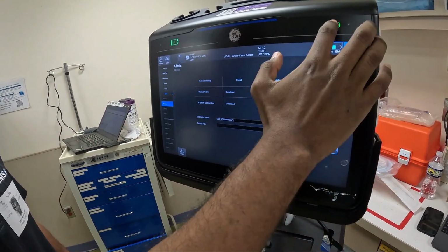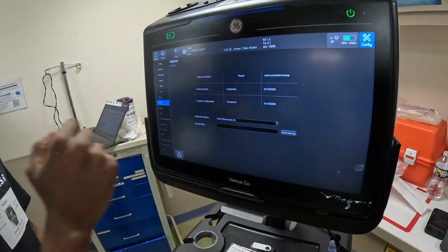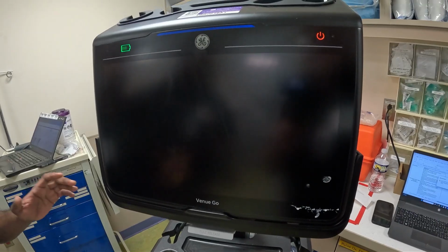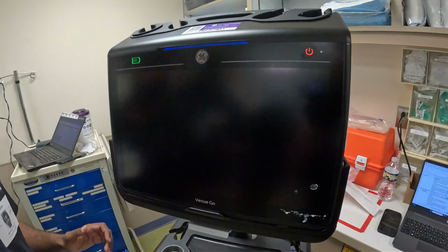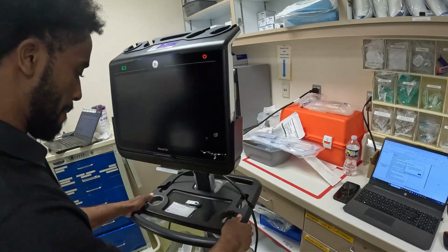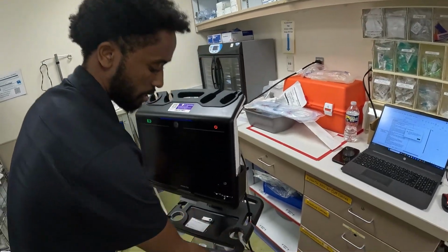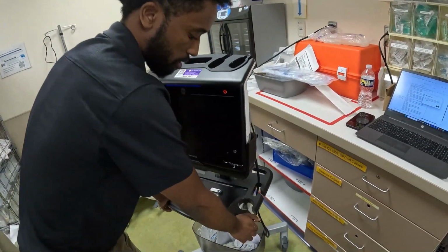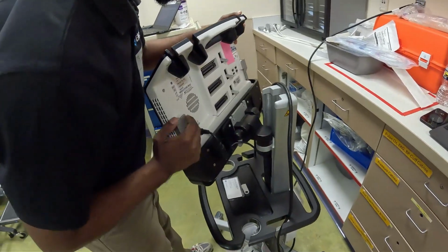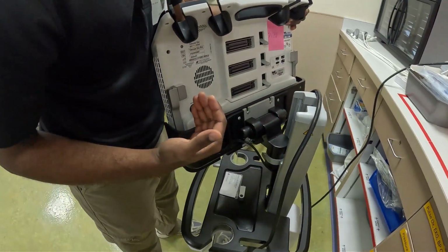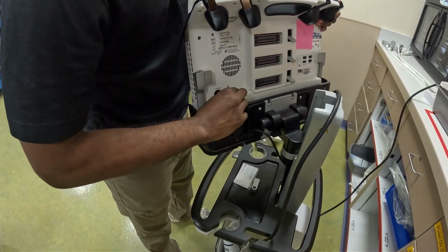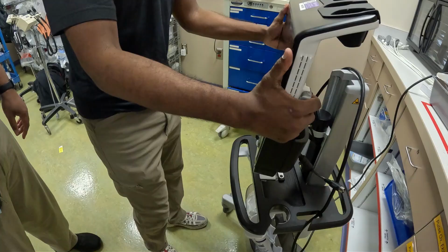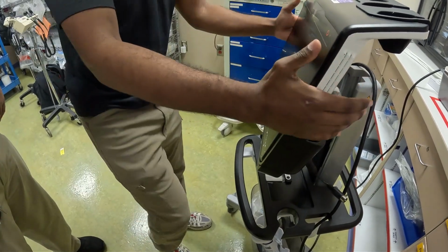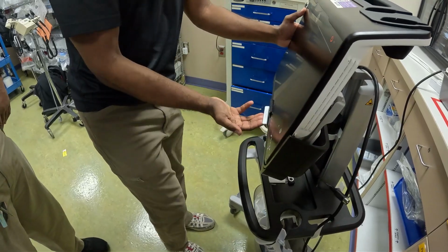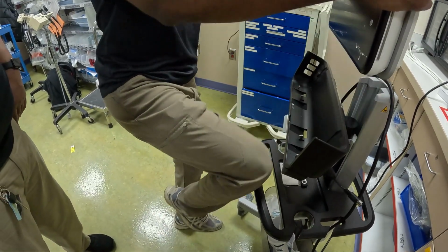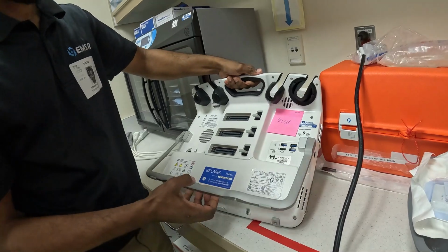Now from there, turn off the device. Once the device is off, you can now proceed to change the batteries. You bring the stand down, clicking these two handles. You got to make sure that all wires connected to the back of the device are disconnected. This is the AC cord, you disconnect that. I like to take the device off with my knee, push this up, and I lift the device on its front actually.